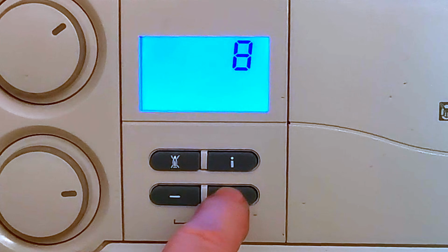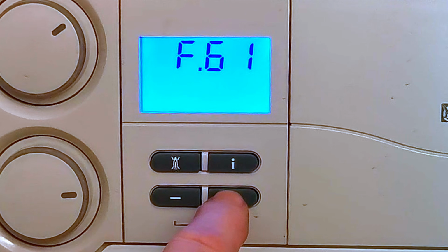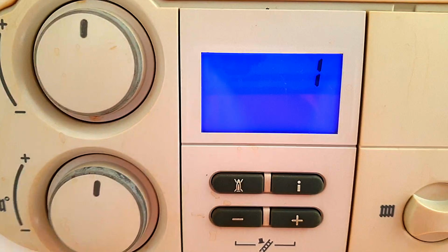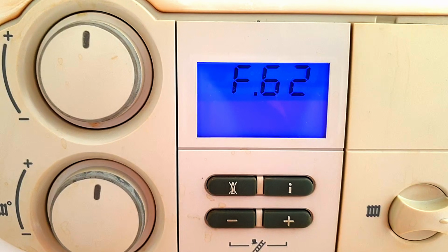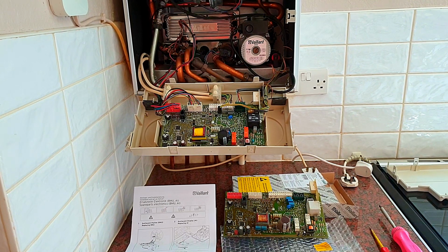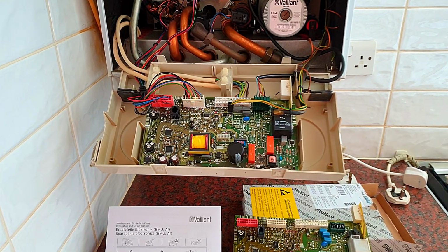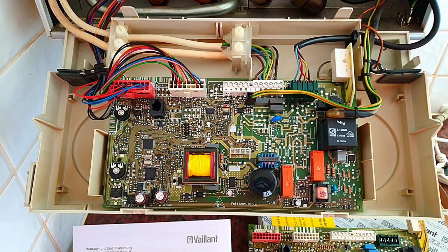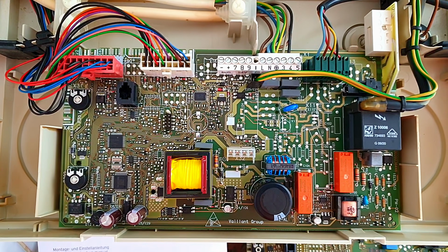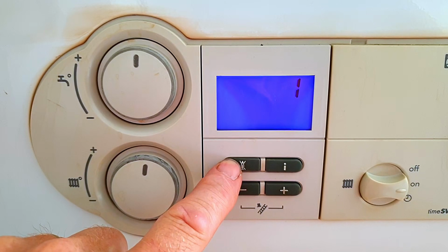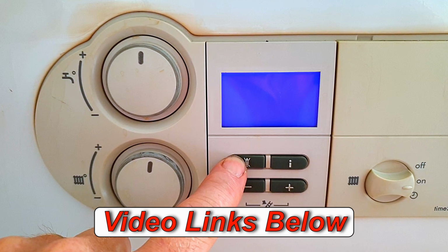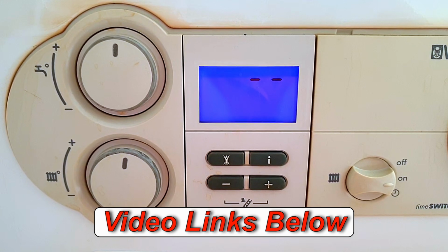Hopefully you're not going to get one of these faults until your boiler's about 10 years old. In the installation manual it says it's a gas valve fault, but I've always found it to be the printed circuit board that's at fault, and not the gas valve at all. Now this is one fault code where you can keep resetting your boiler. It'll probably get worse over time, and then the only thing you can do is to call a gas registered engineer to come and take a look at your boiler.